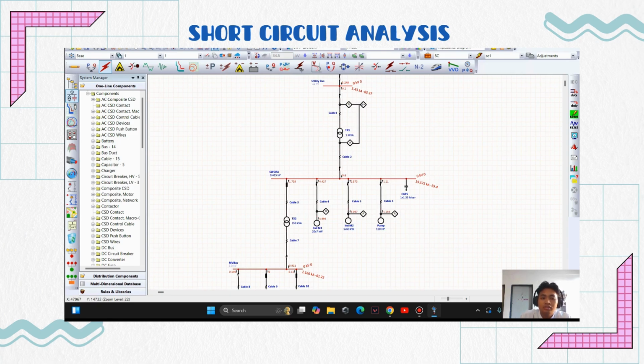This is because the fault current at the SWGRA is contributed not only from the upstream utility bus via the network feeder and transformer, but also from the downstream, which we can see here, with cable 4, cable 5 and cable 6 being inductive load, and adding the capacitor bank here.